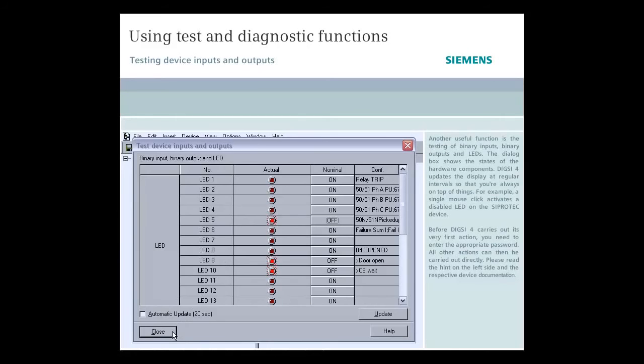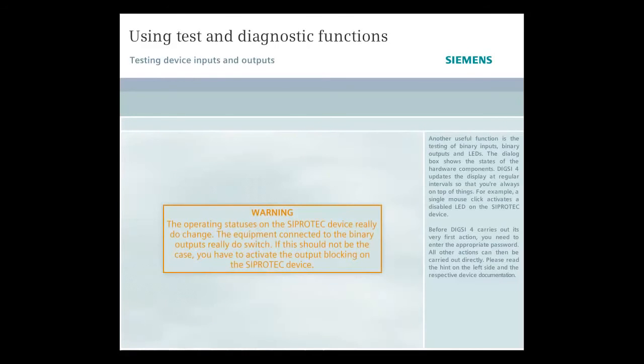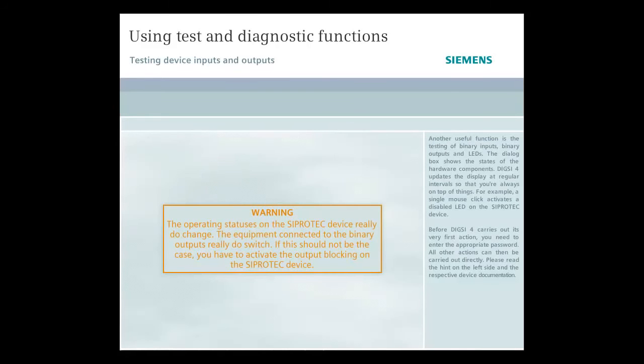At this point, we must make it clear that the operating statuses on the SIPROTEC device really do change. The equipment connected to the binary outputs really do switch. If this should not be the case, you have to activate the output blocking on the SIPROTEC device. Please read the respective device documentation for this.